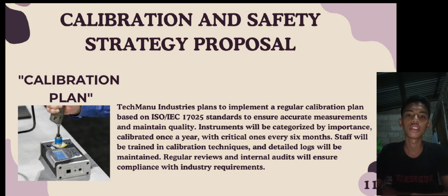Calibration and Safety Strategy Proposal. Calibration Plan: TechManu Industries plans to implement a regular calibration plan based on ISO/IEC 17025 standards to ensure accurate measurements and maintain quality. Instruments will be categorized by importance, calibrated once a year, with critical ones every 6 months. Staff will be trained in calibration techniques, detailed logs will be maintained, and regular reviews and internal audits will ensure compliance with industry requirements.